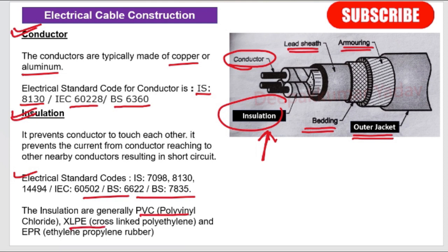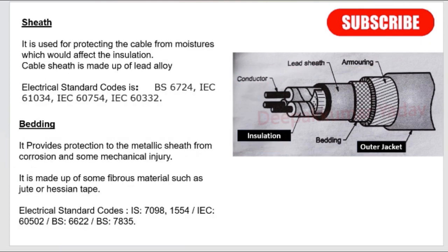The insulation materials are generally PVC (polyvinyl chloride), XLPE (cross-linked polyethylene), and EPR (ethylene propylene rubber). After the insulation, the next protective layer is the sheath. It is used to protect the cable from moisture, which would affect the insulation. The metal sheath is made of lead alloy. Electrical standard codes are BS 6724, IEC 61034, IEC 60754, and IEC 60332.